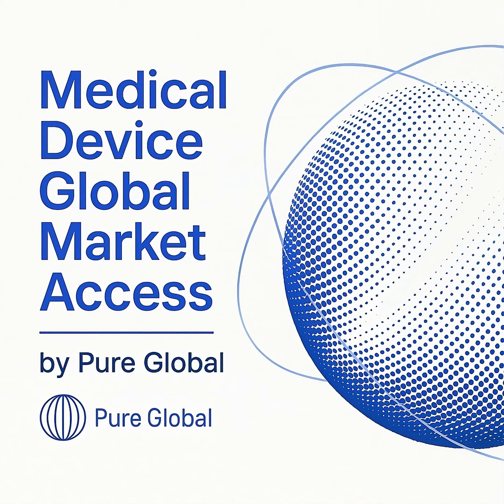At the core of every regulatory submission is the technical documentation, often called a technical file for CE marking in Europe or a design dossier. This comprehensive file is the evidence that your device is safe, performs as intended, and complies with all applicable regulations. Key components include a detailed device description with its intended purpose, specifications, and variants.